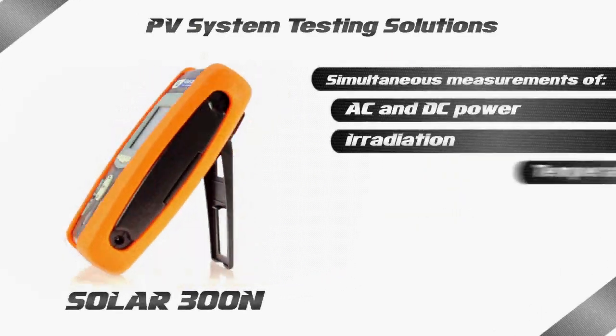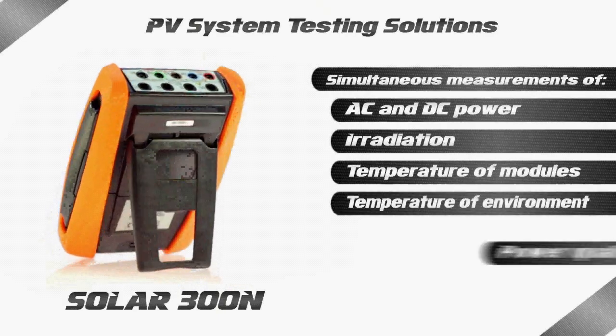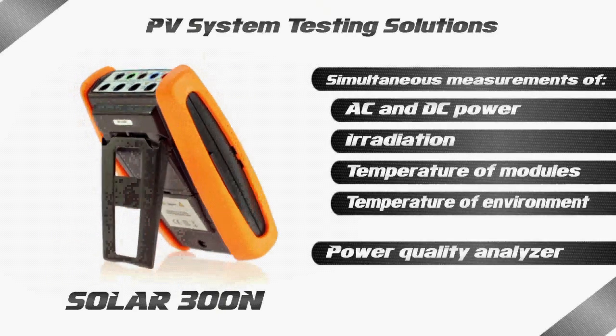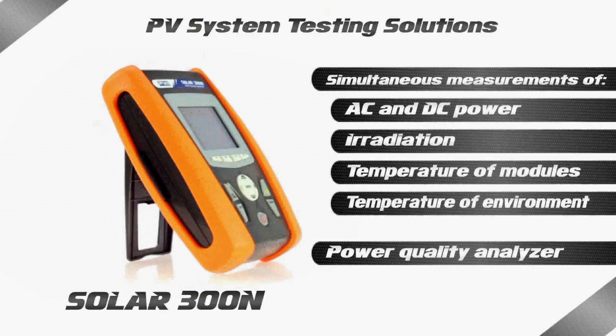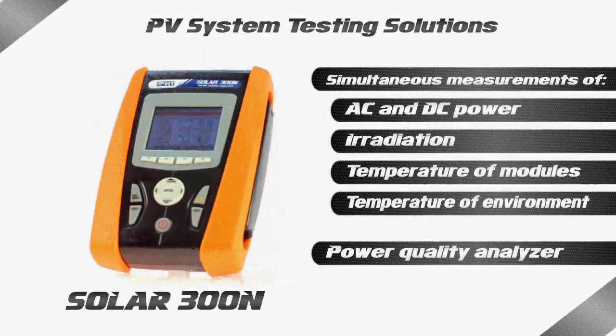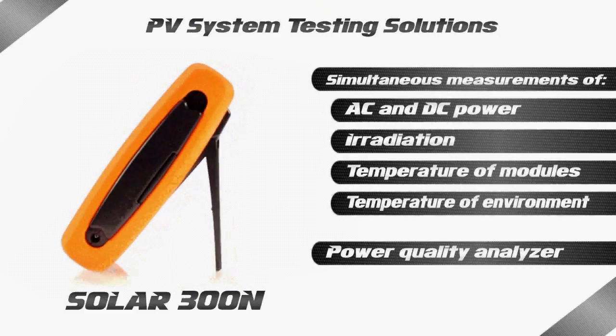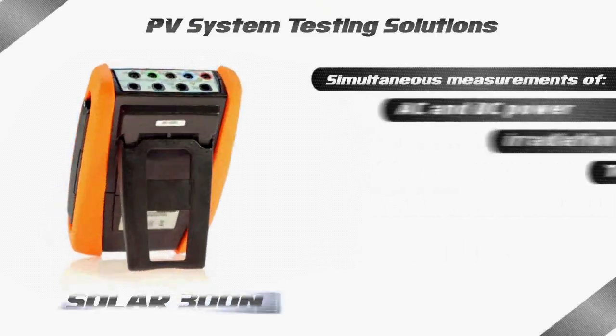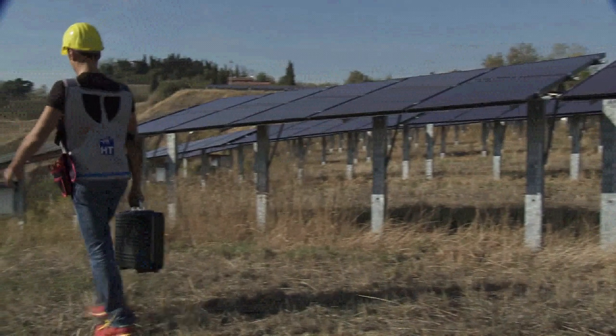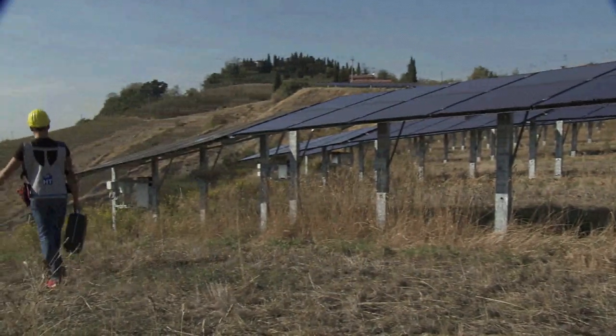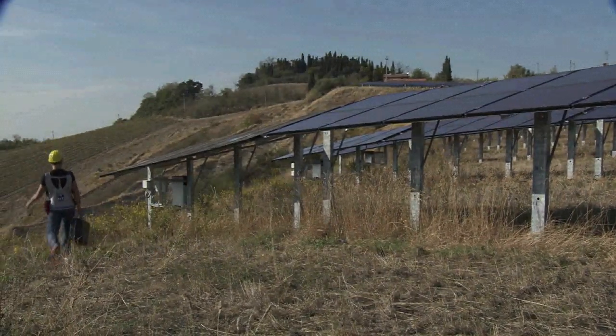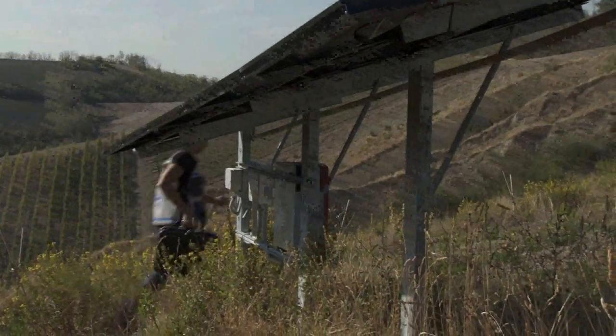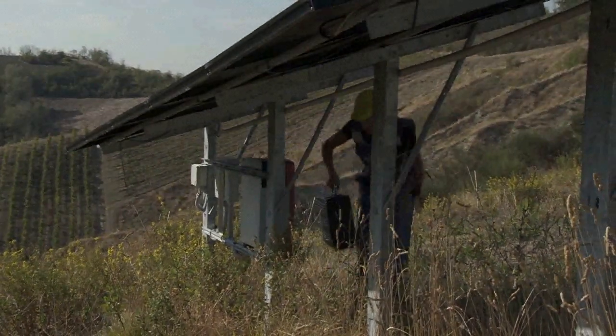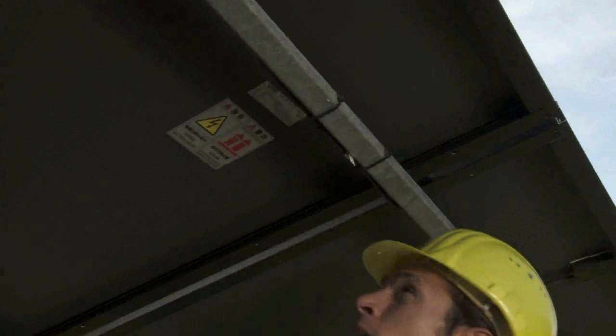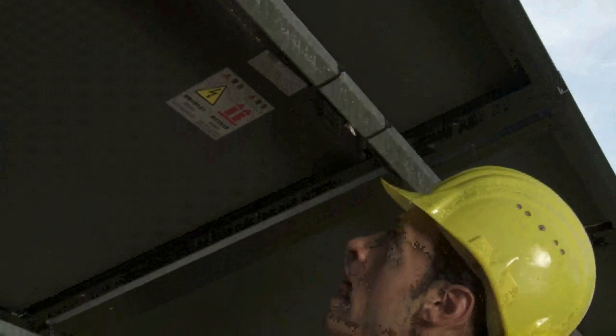HT presents the new SOLAR300N instrument, which is ideal for carrying out a complete efficiency test of all components of a photovoltaic system. SOLAR300N is also a professional network analyzer which allows the detailed recording of all parameters of the electric network: harmonics, voltage dips and peaks, micro-interruptions, inrush currents, unbalance and flicker. The instrument also analyzes the quality of the electric supply in compliance with the provisions of European Standard EN 50160.